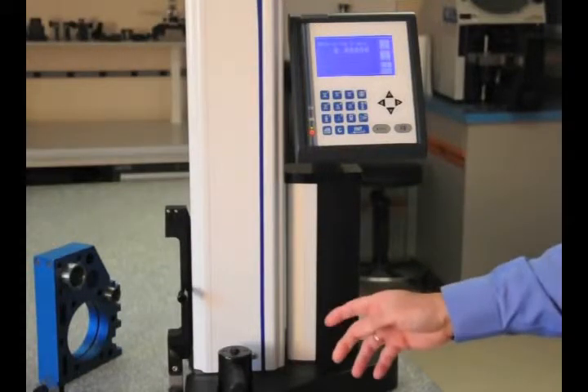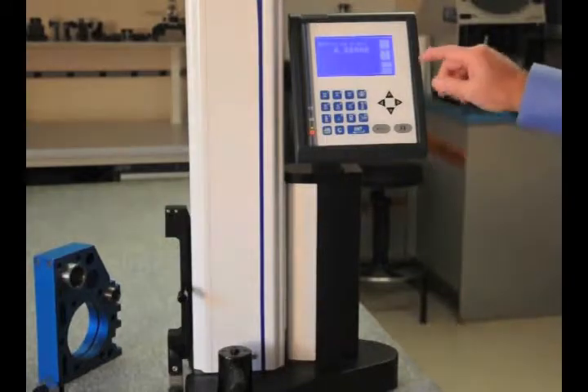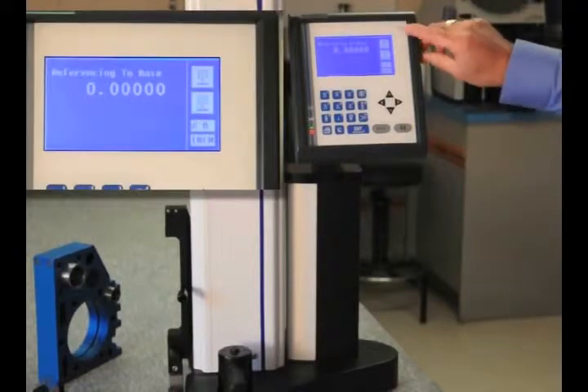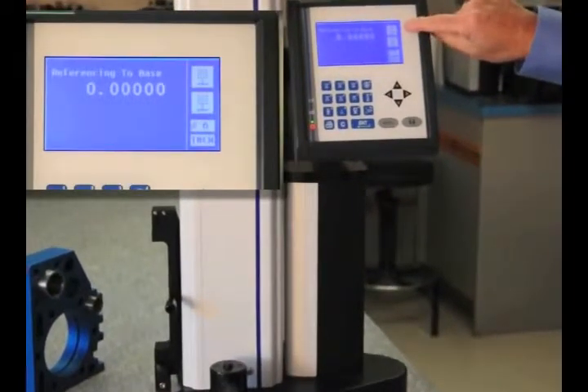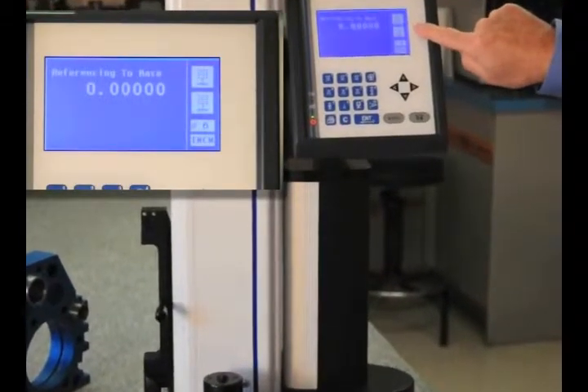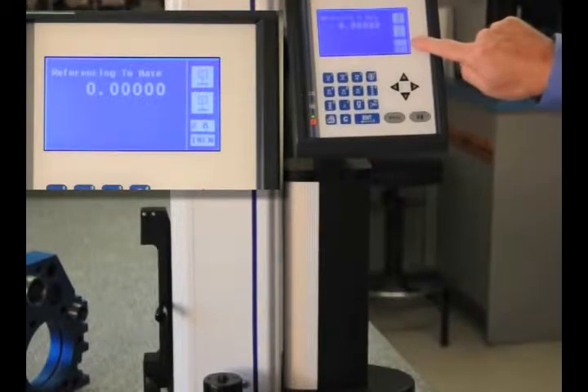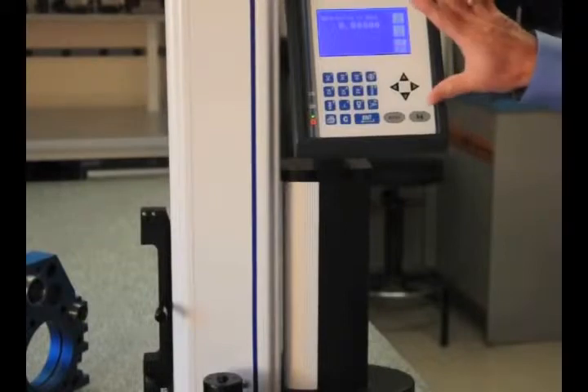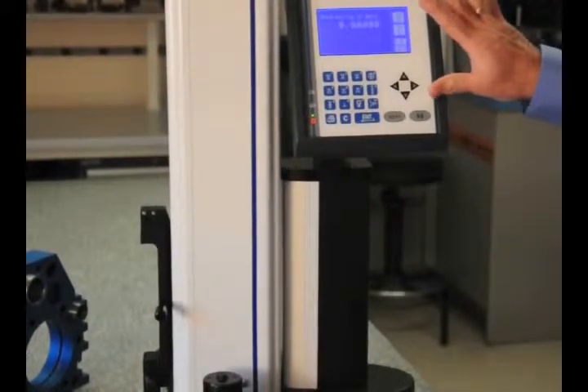It's motorized and it's going to reference itself to the surface plate and set zero on the main reference. Now we've got that zero off of the surface plate. You'll see here on the display the zeros. We've got 50 millionth resolution. You'll see the reference up here is our zero reference. The probe diameter is six millimeters and we're in inch mode.